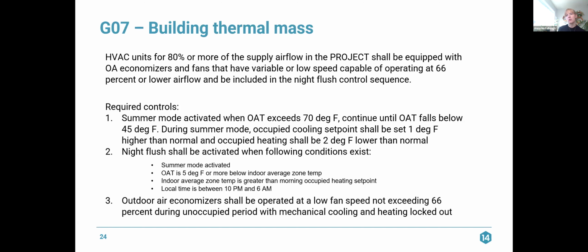And the local time is between 10 p.m. and 6 a.m. Then you have to activate this night flush, where we're using the outdoor air economizers at a lower than maximum speed to flush out the warm, hot air, use that cool outdoor night air to cool the building down. Outdoor air economizers shall be operated at a low fan speed, not exceeding 66% during the unoccupied period, with mechanical cooling and heating locked out. We're not heating and cooling for this night flush.